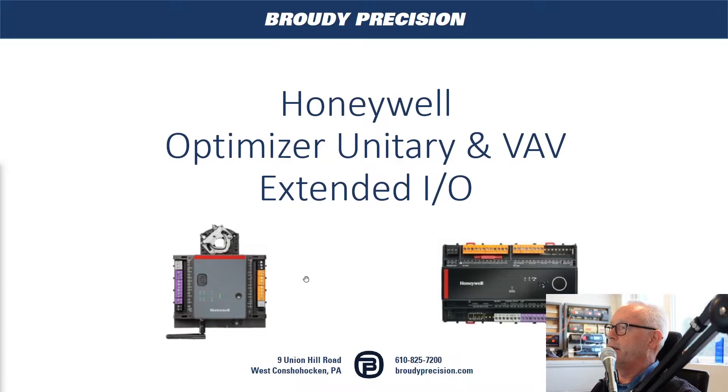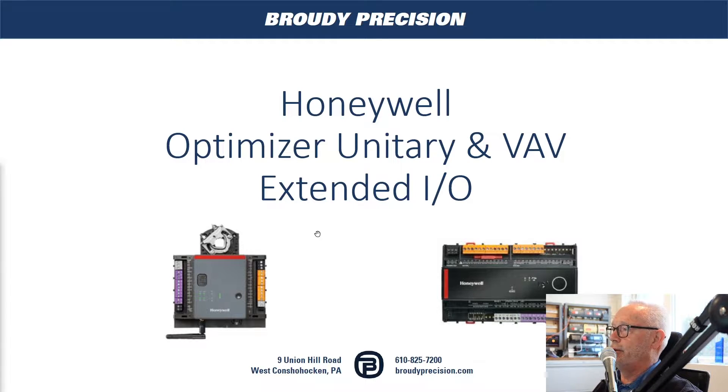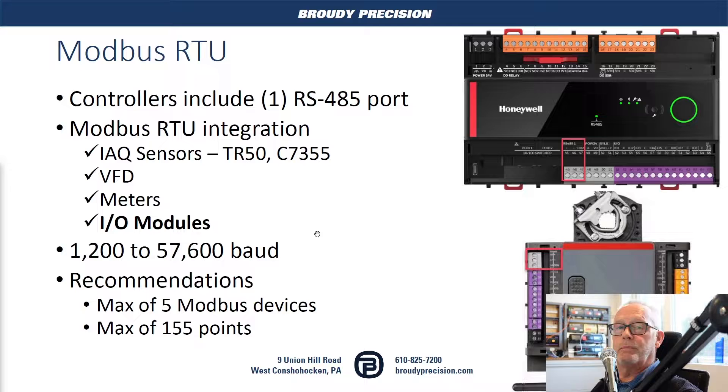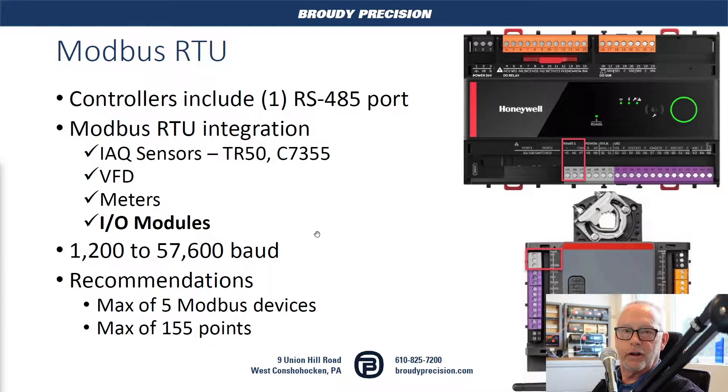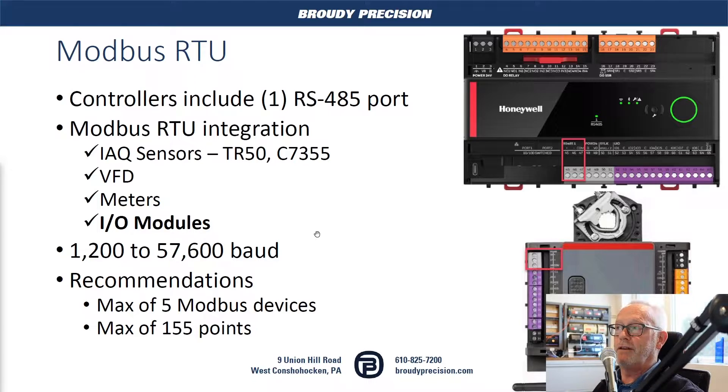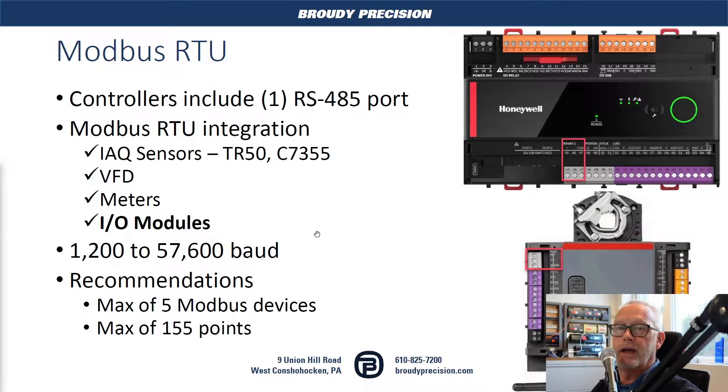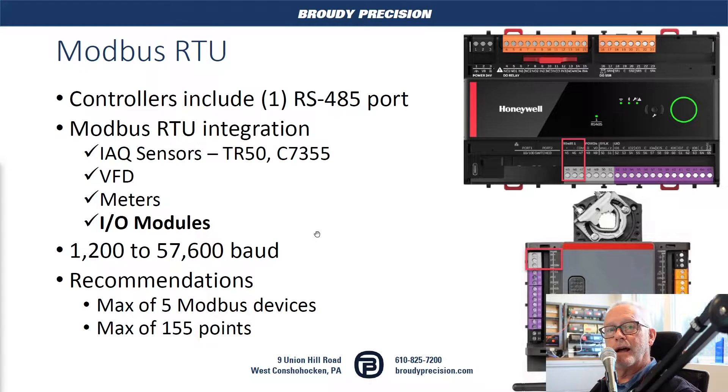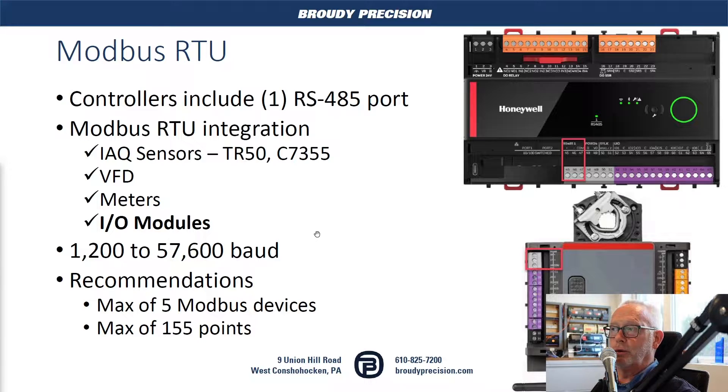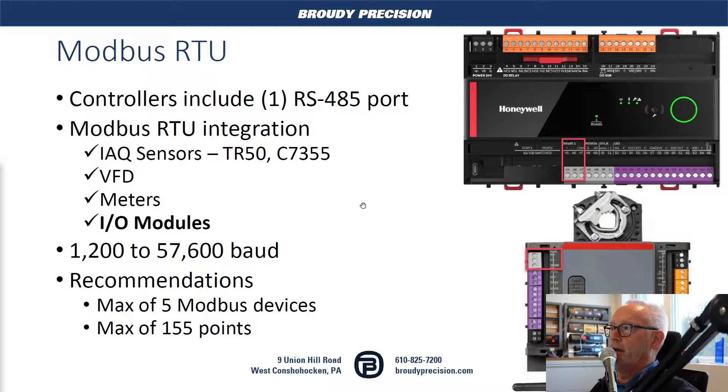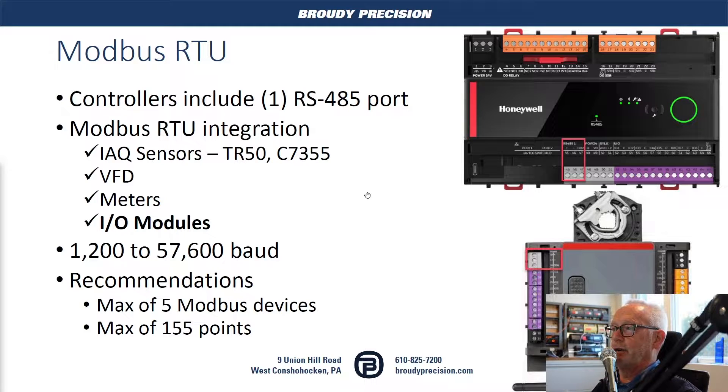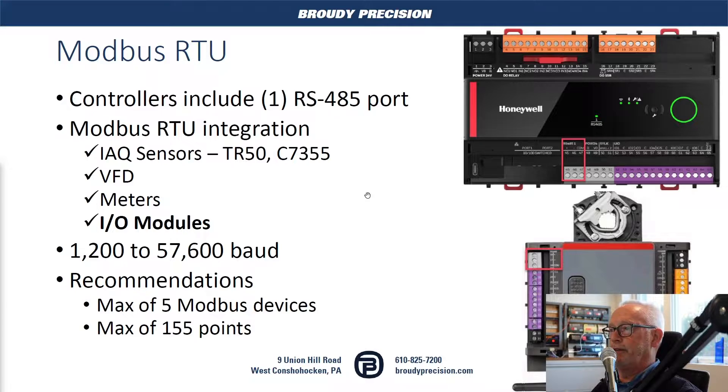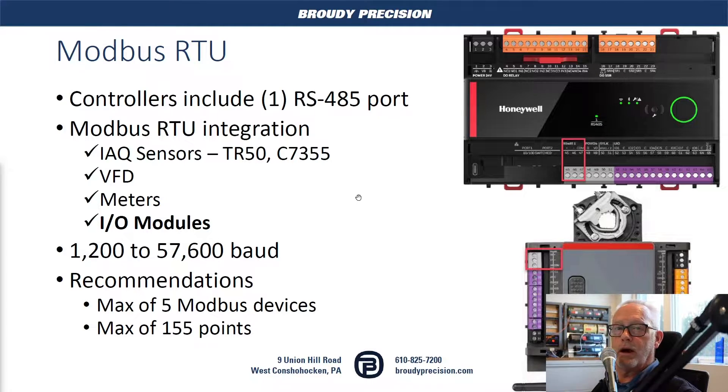Let's go ahead with some information first to get a little background before we actually go live into the workbench. The Optimizer Unitary and VAV controllers have a 485 port that allows for Modbus RTU. The intent of that port is to extend the ability to have other devices connect to it, such as IAQ sensors, VFDs, meters, and also I/O modules.